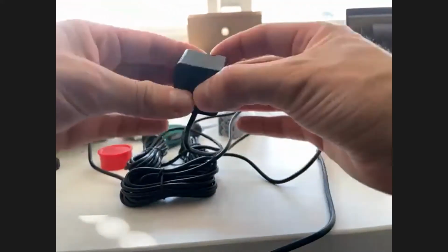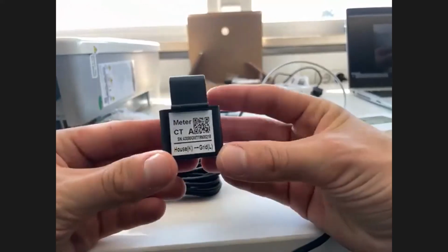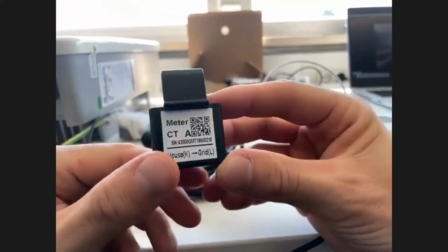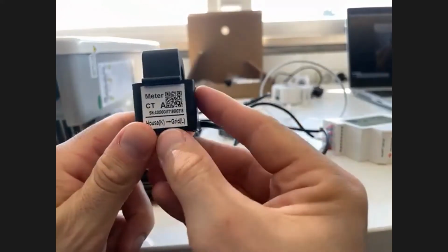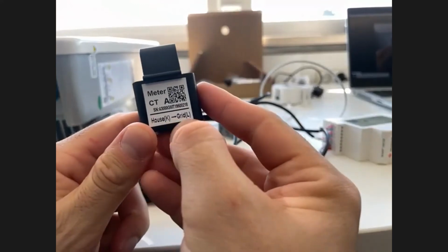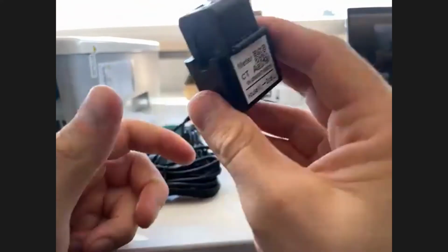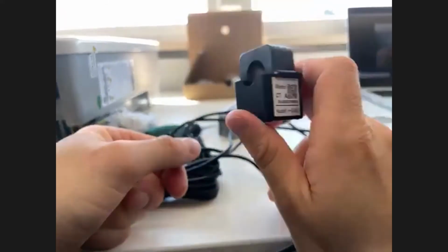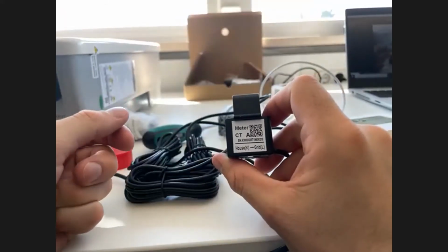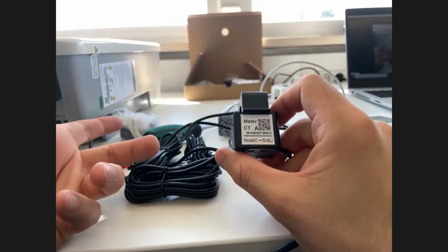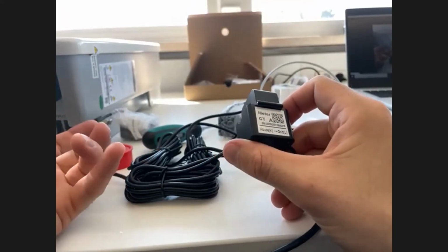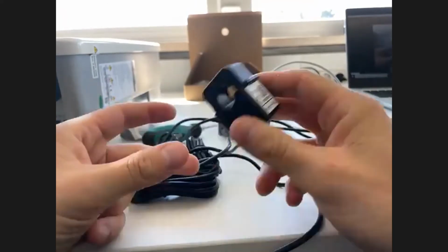Yeah. And here it even says on the CTs, it says CTA, and it says from K to L. So it means that you need to connect it from house to the grid, from the loads to the grid. And these need to be connected just before the grid connection point. So before the house meter. There's usually a house meter measuring the energy, so just connect it to the correct phase before that.